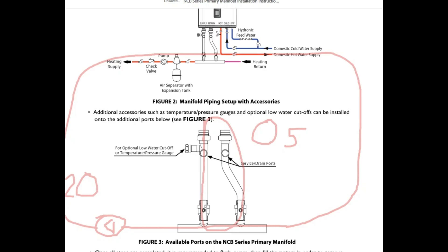And whatever water volume cannot make it in there. So if we have 20 gallons a minute in this secondary loop, and we only can move five gallons a minute through this primary loop here, what's going to happen is about 15 gallons a minute is going to be flowing through, straight through like I suggested. But five gallons is going to be pulled off, reheated and sent back in again. So eventually, as this loop continues to go around and around, it's going to start heating up more and more and eventually gets up to the BTUs that we actually need to deliver to the home to heat the home up.